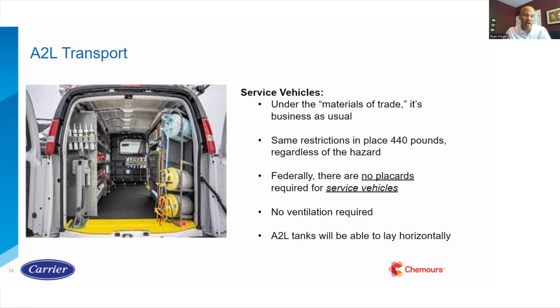The reason that they had that rule is the relief valve, they want to be in contact with gas, not liquid. So by having it in the upright position, that would be the case. But they are going to let you put it horizontally, but it would be intelligent for you to rotate the tank so the relief valve is over here at the top end instead of at the bottom end, so it's still in contact with vapor and not so much with liquid. But you don't have to have the vertical storage anymore.